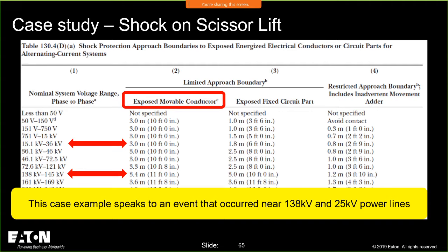Now let's take a look at the restricted approach boundary over here. If it's less than 50 volts, I'm not worried about it. If it's between 50 and 150, a good example of between 50 and 150 is a receptacle, right? It's a 120 volt item in the power distribution system. Remember what the restricted approach boundary is: anything that I bring into that has to be insulated, and I have to have my gloves and whatnot. It says avoid contact. So I simply have to avoid contact with those energized parts when I'm below 150. And beyond that, I am into 2 foot 2 inches for that boundary.